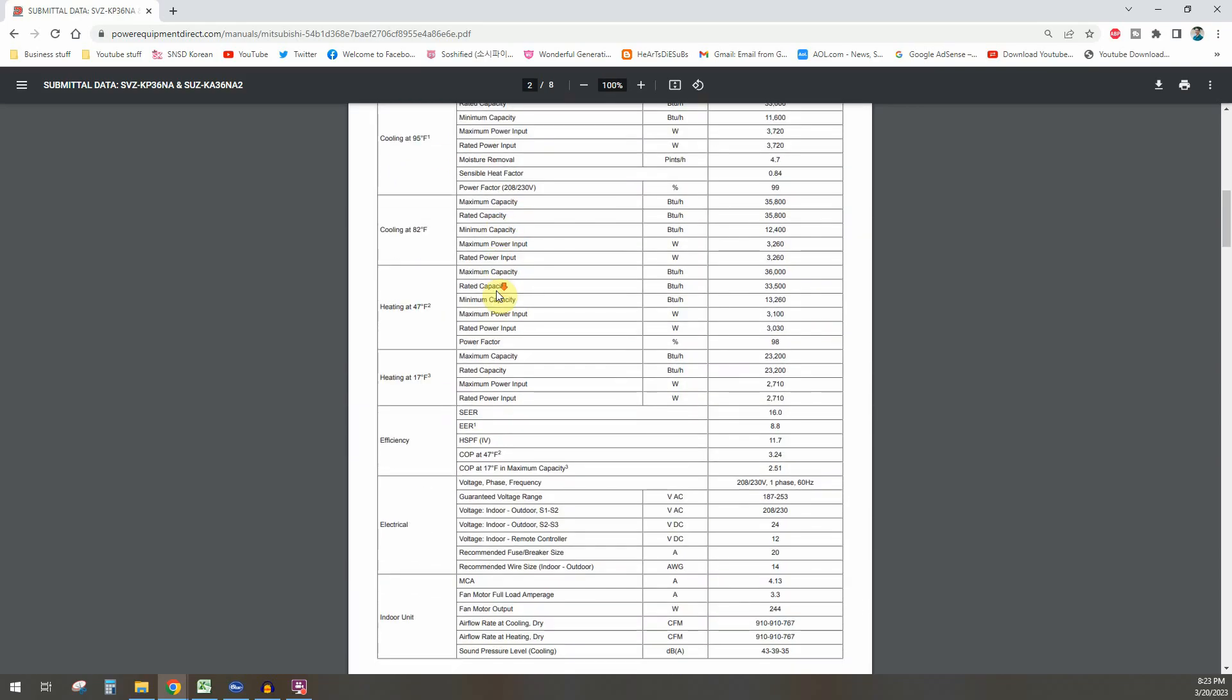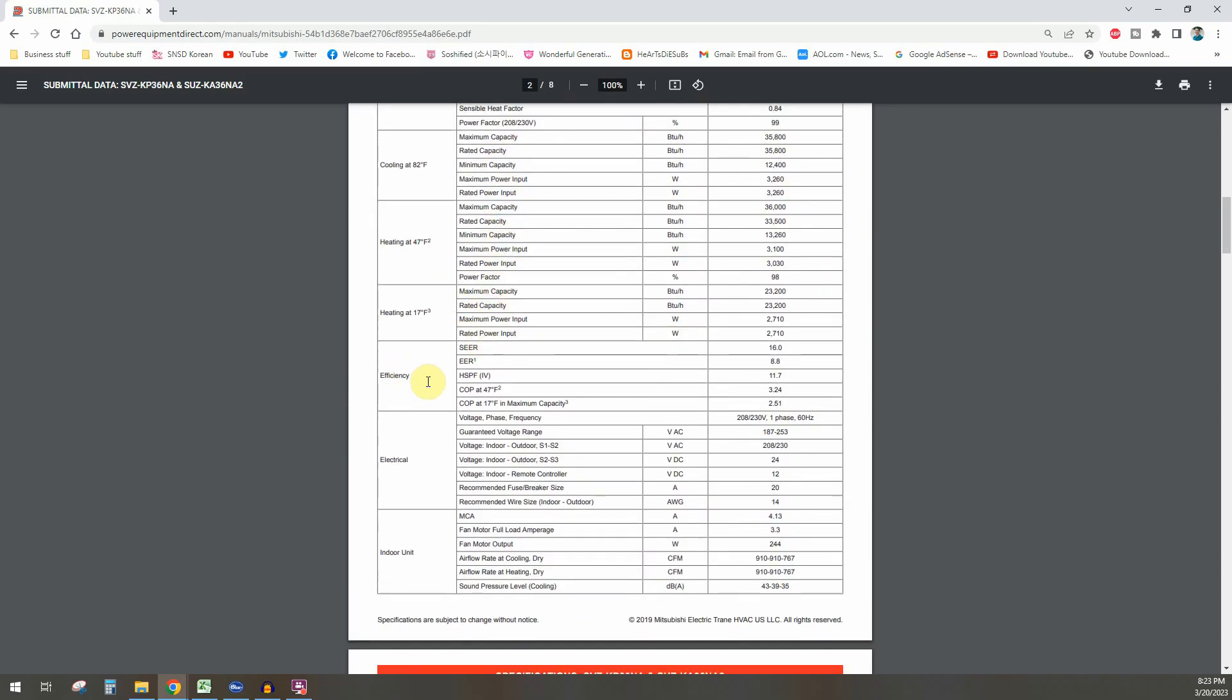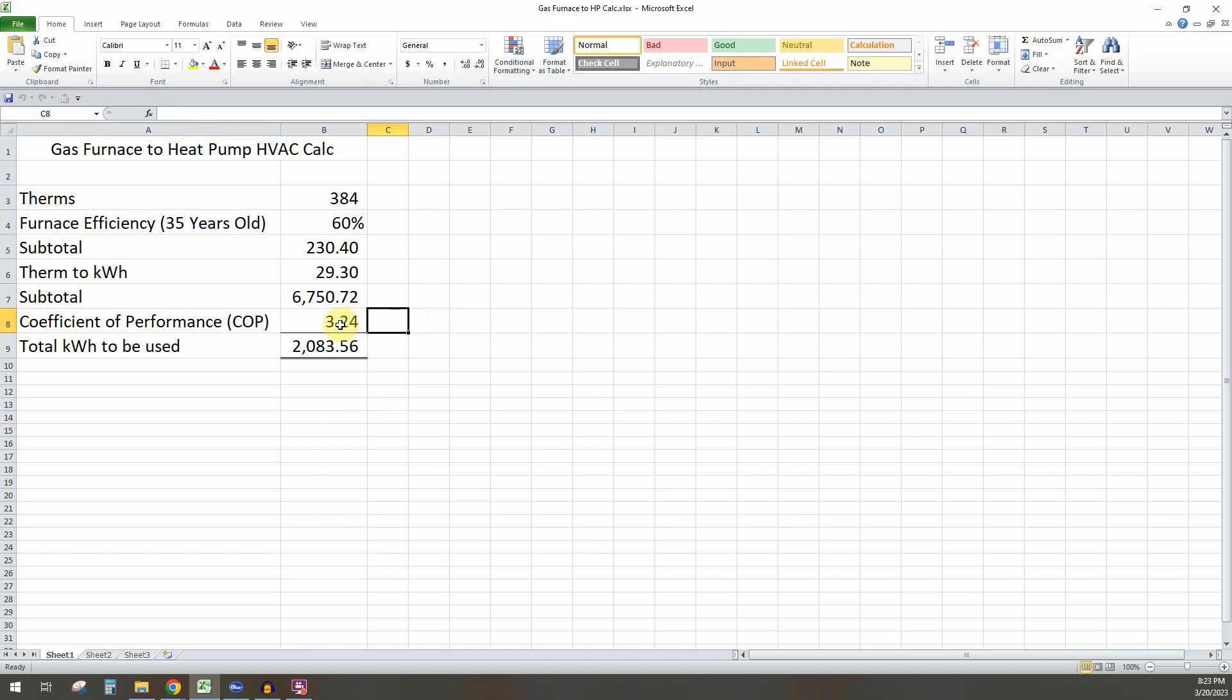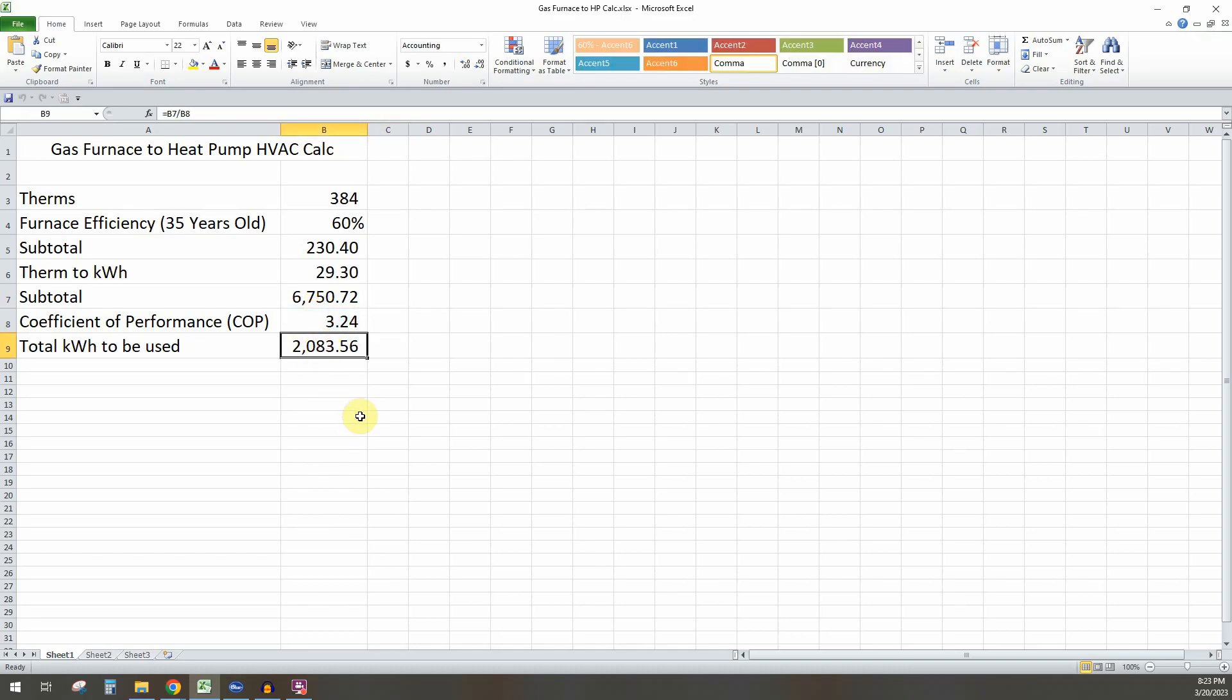So if we go down to the efficiency portion, you see the COP at 47 degrees is 3.24. So you take that number, divide these two, and you come up with about 2,100 kilowatt hours of energy use.